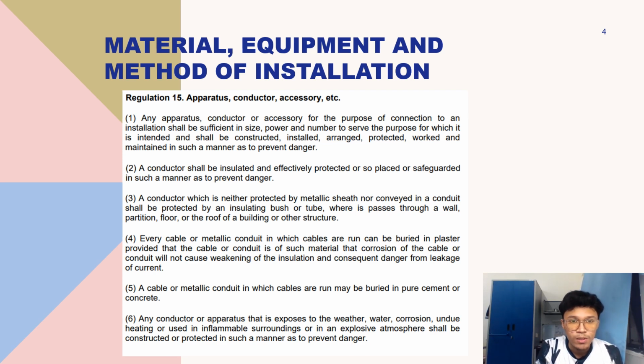Number 2, a conductor shall be insulated and efficiently protected, also placed or safeguarded in such a manner as to prevent danger. Number 3, a conductor which is neither protected by metallic sheath nor conveyed in a conduit shall be protected by an insulating bush or tube where it passes through a wall, partition, floor or the roof of a building or the structure. Number 4, every cable or metallic conduit in which cables are run can be buried in plaster provided that the cable or conduit is of such material that corrosion of the cable or conduit will not cause weakening of the insulation and consequent danger for leakage current.